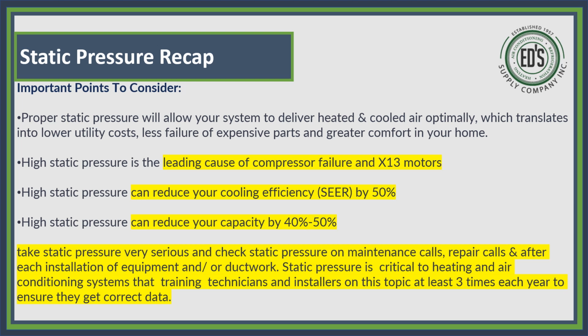Just because it's brand new doesn't mean that condensing fan motor is pulling enough RPMs to get the heat off the furnace or off the coil. Or let's say your condensing coils are dirty. This is the same problem. That's why your capacitors will go out. That's why the condensing fan motors go out. That's why compressors go out. Coils are dirty or the fans are not doing their job to pull that heat off.